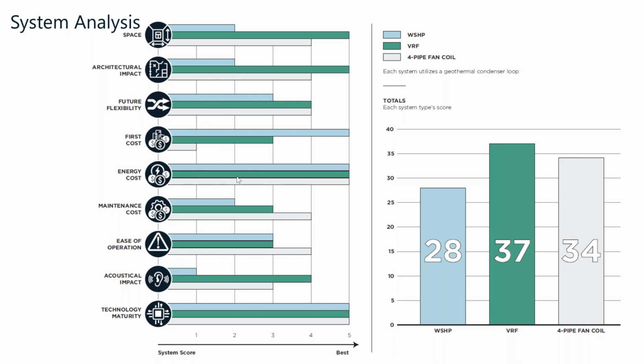The systems we used for the VRF are actually a water-cooled variable refrigerant flow system. The water-cooled comes from the geothermal system. They are water-cooled and both cooled, and we have heat rejection as well that goes in. The variable refrigerant flow has energy recovery within the individual refrigerant components. And that system is used to heat and cool the building. It is worth noting that the VRF system we have is independent of the ventilation air system. So those systems are decoupled.